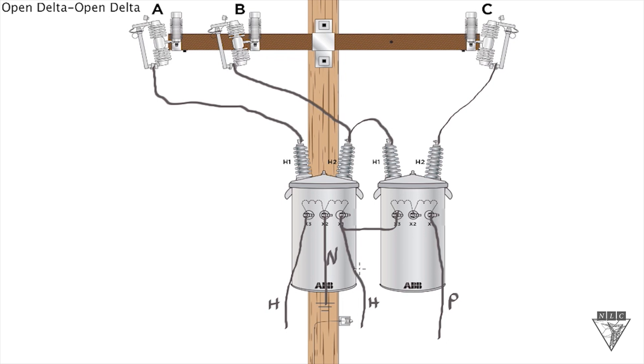With this open bank, usually you'll see these open banks used like this where the single phase load is your primary load on the system. With a single phase load you're going to use this transformer for your neutral connection and then your two hot legs.